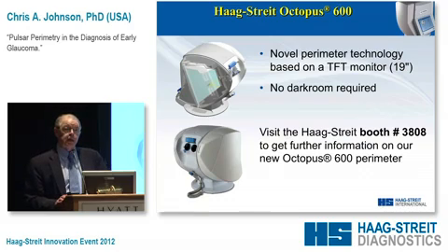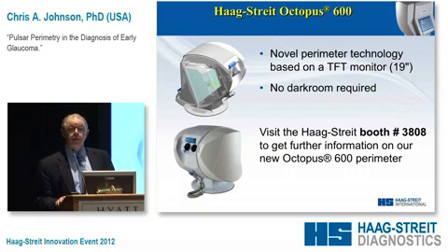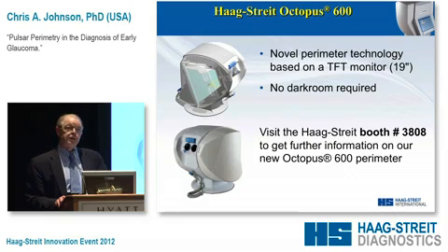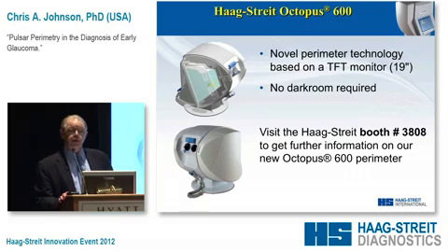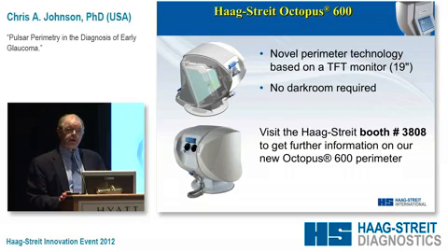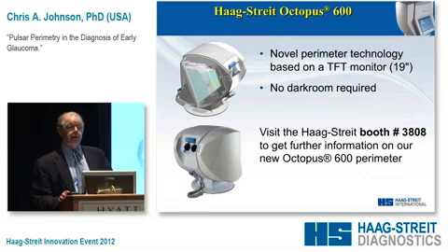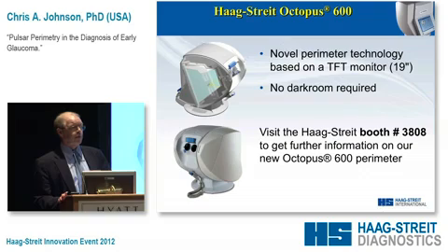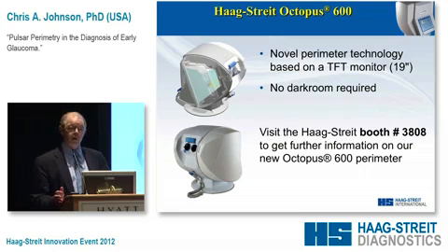It doesn't require any particular lighting conditions—you don't need a completely darkened room. I'd like to present some findings, as we had an earlier version before it was implemented in the Octopus 600. I was interested in how reliable the calibration is and how robust it is to the nuances that occur in a clinic. In a laboratory setting, devices always work best for the person who developed them, but in clinics throughout the world, quite a wide variety of changes can occur.